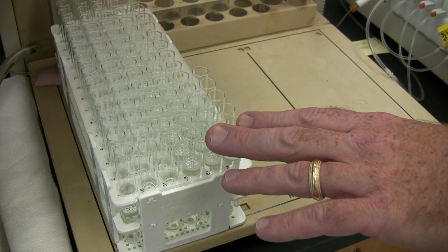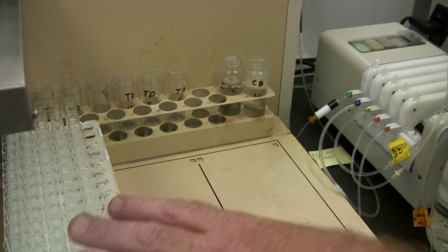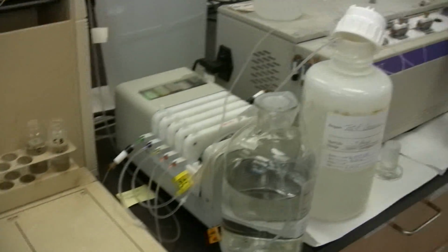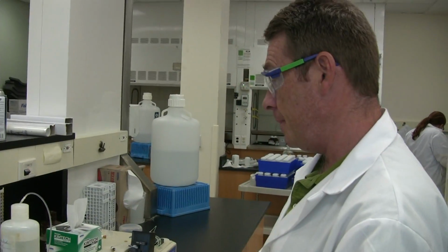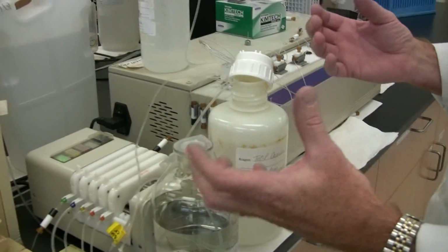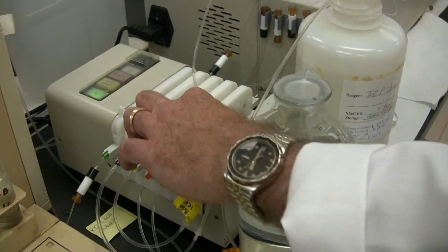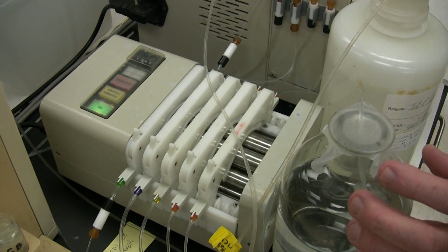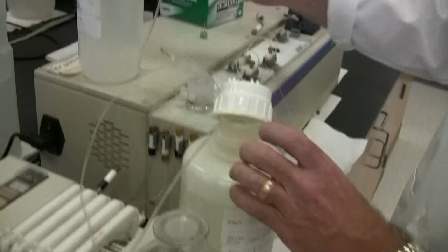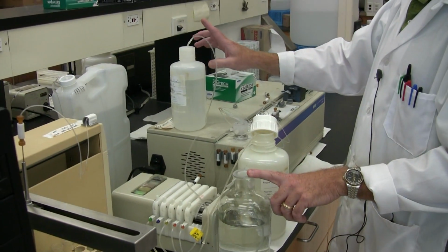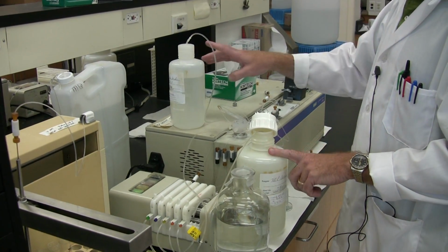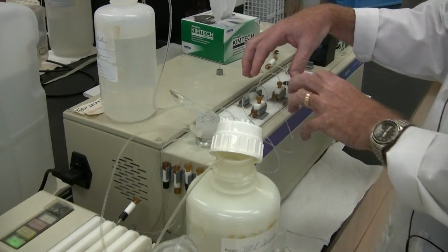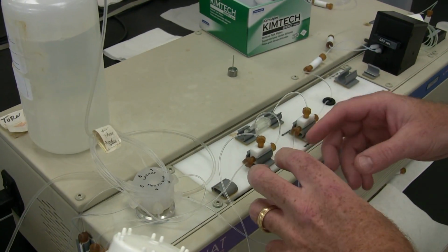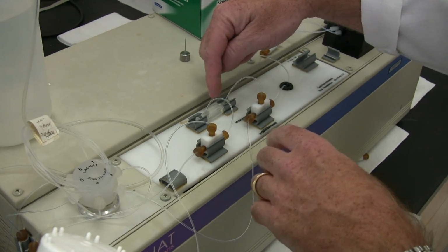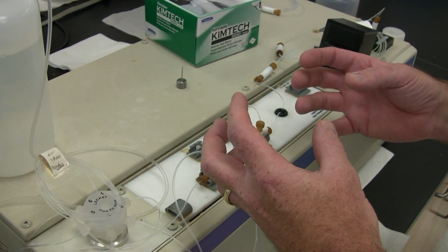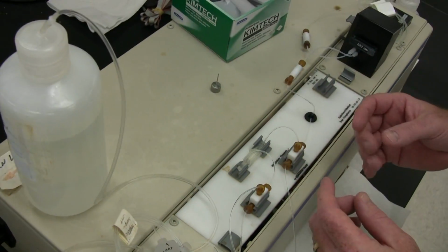Basically, this is a sampler, which is going to bring samples, whether it's standards, which I have back here, or unknowns, to our instrument to analyze. Instead of having a test tube where we put known amounts in, we have different size pump tubes that are proportioned to bring in the right amount. These two mix together as a color reagent. This is just a carrier. So we have a color reagent here and here that come together, and a carrier, and those all come into this manifold. Instead of mixing stuff up in a test tube, we have things proportioned into T's and a little mixing coil, and everything mixes together so we have the right mix. So the color reagent and carrier are all ready for the sample.